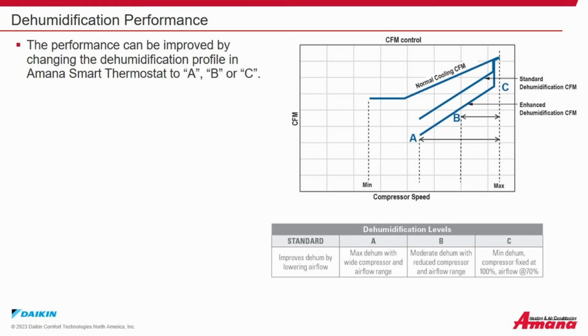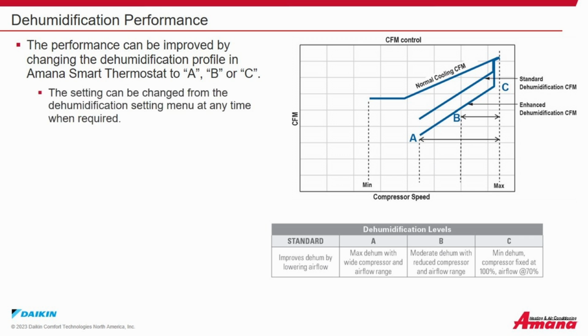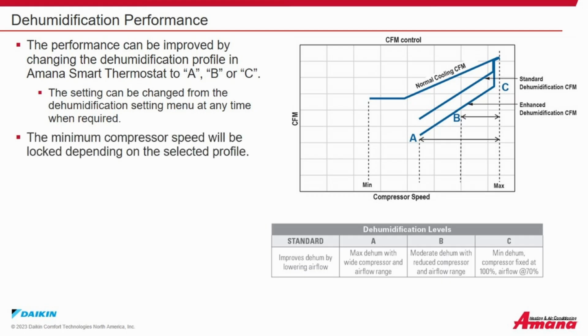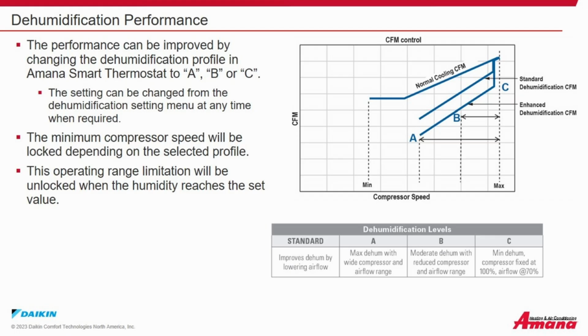Dehumidification performance. The performance can be improved by changing the dehumidification profile in the Amana Smart Thermostat to A, B, or C. The setting can be changed from the dehumidification setting menu at any time when required. The minimum compressor speed will be locked depending on the selected profile. The operating range limitation will be unlocked when the humidity reaches the set value. There must be a call for cooling and a demand for dehumidification.